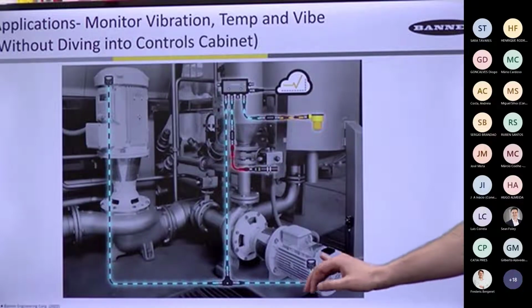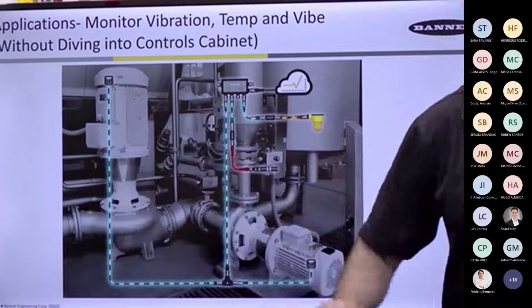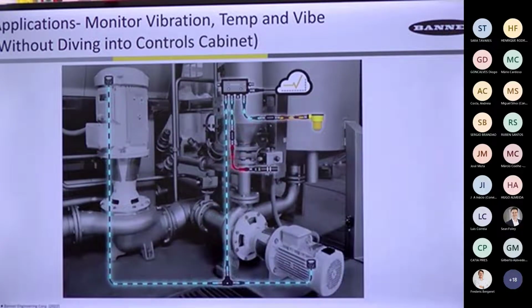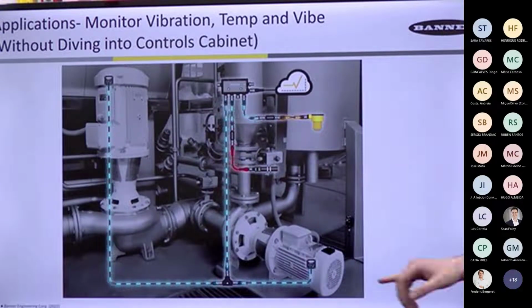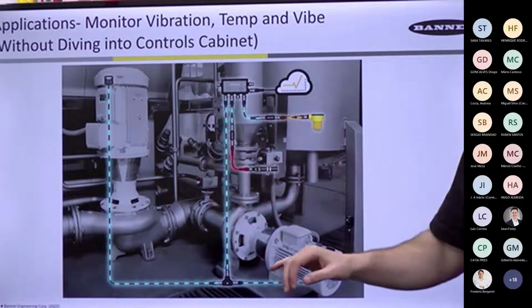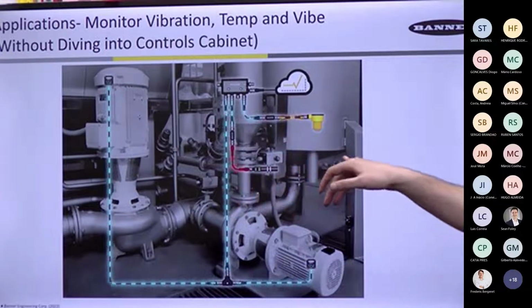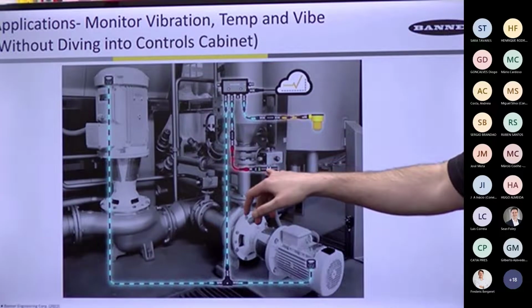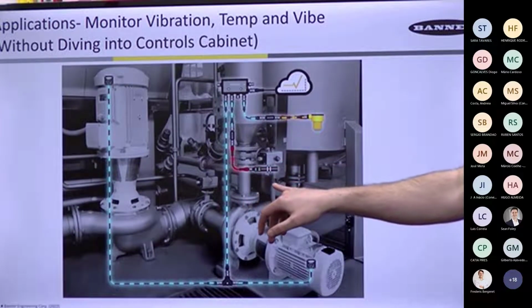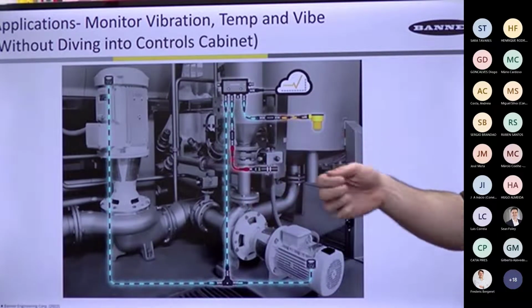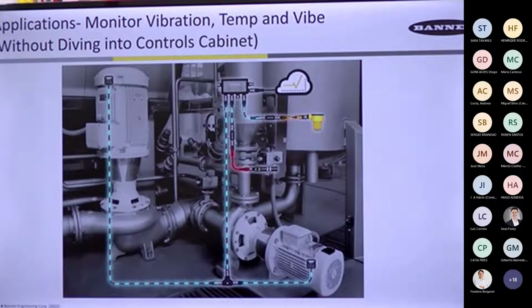Essentially, here we have two motors. We're monitoring those motors' vibration and temperature, taking it into a single port of the DXM R90. But we also want to monitor the surface temperature of an object. Here we have a contactless temperature sensor, and we're able to point that sensor at an object surface and continuously monitor the temperature of that surface, converting it over to that unified serial protocol.